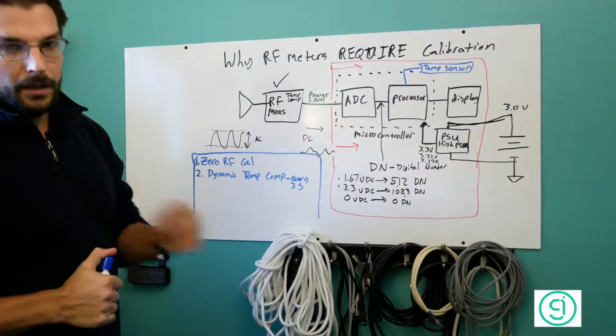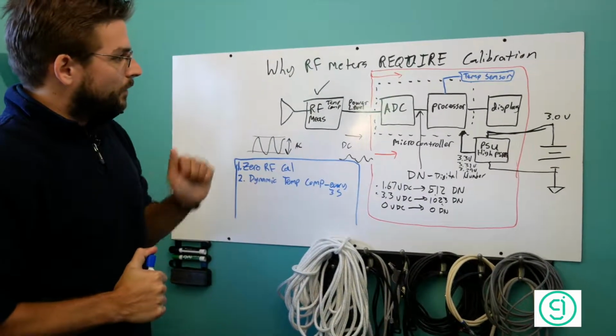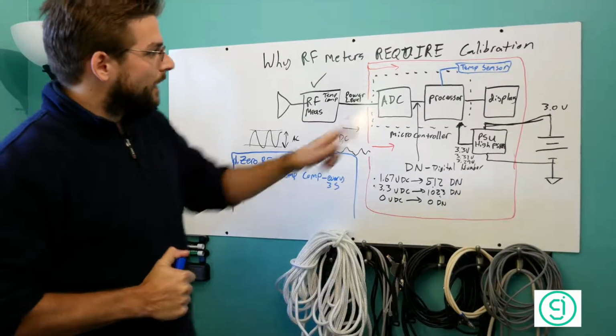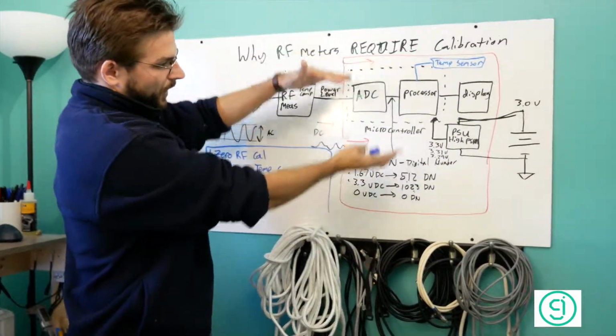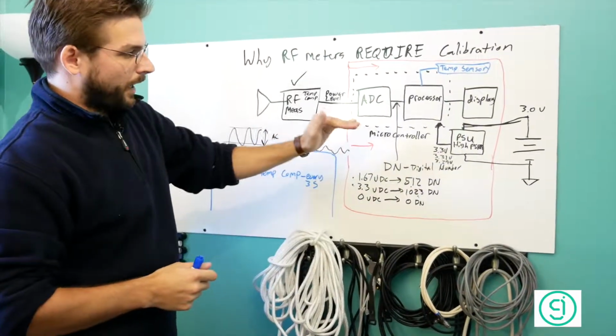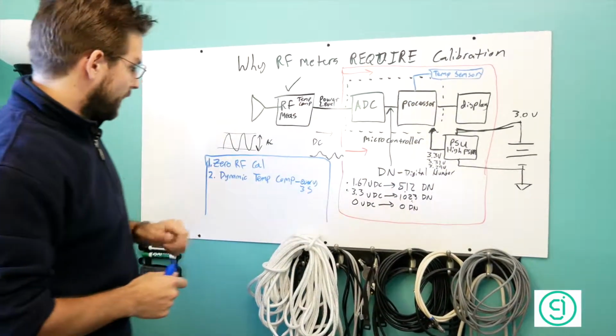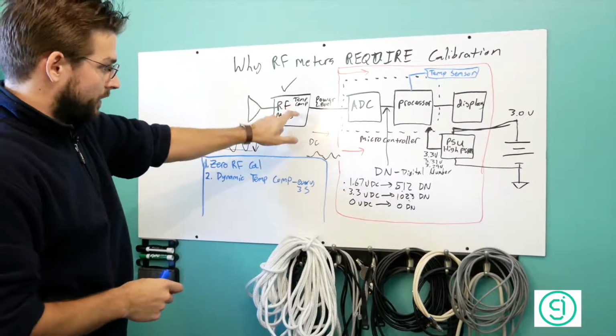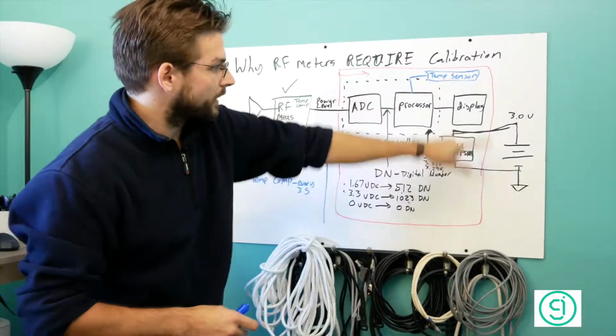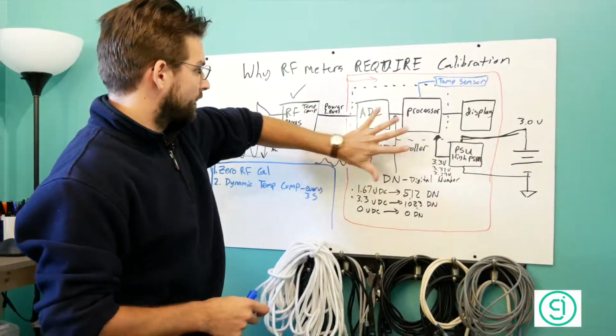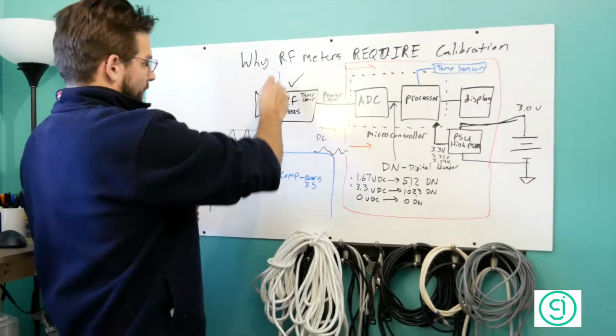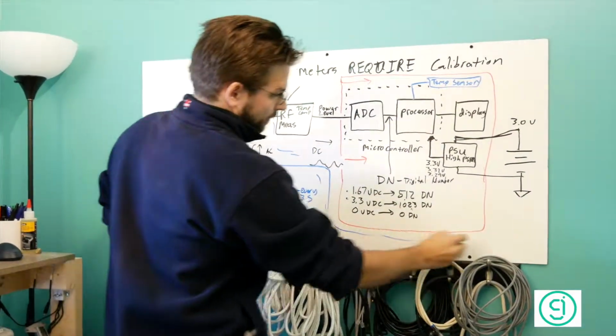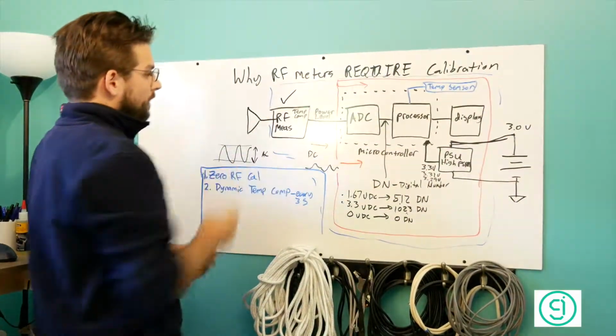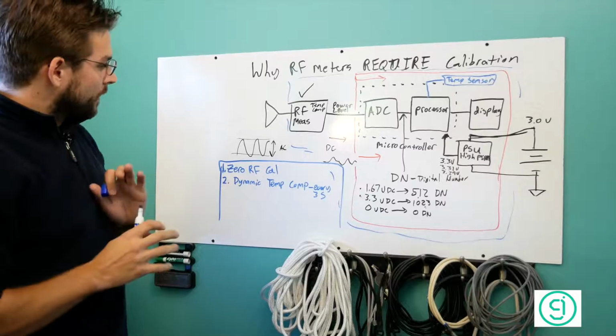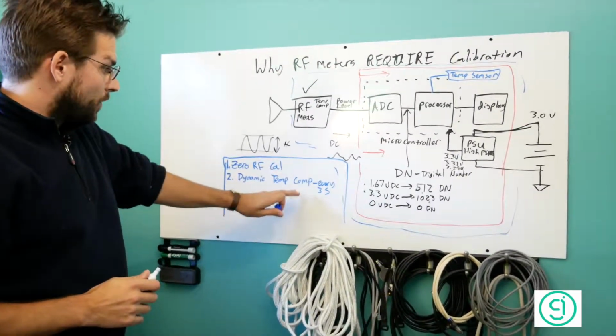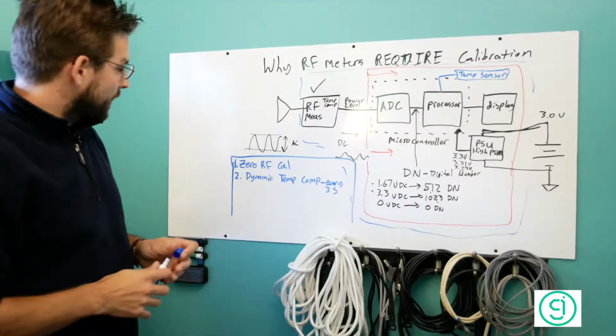So if your device is really hot and you pull it off the dash of your car and you turn it on, as it's booting, when it's doing its self-calibration, it's going to look at what the temperature is, and then adjust the measurement offset to the new 0 cal value at the ambient temperature the meter is at. This has very little to do with the RF amplifier. It mostly has to do with the rest of the system. You have to temperature compensate this stuff too. But because we've done our temperature compensation on the entire device, the whole enchilada, even if we have temperature drift in our RF amplifier, we calibrate it out. And this happens all the time while the meter's running. You don't have to do anything. It's just taken care of automatically.